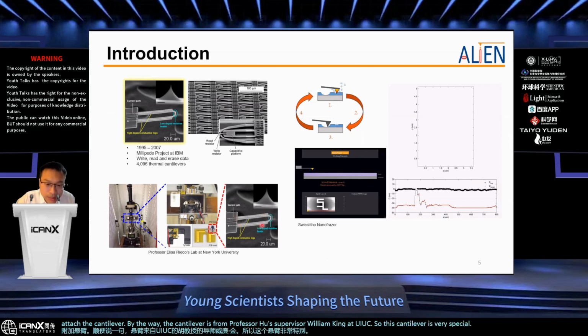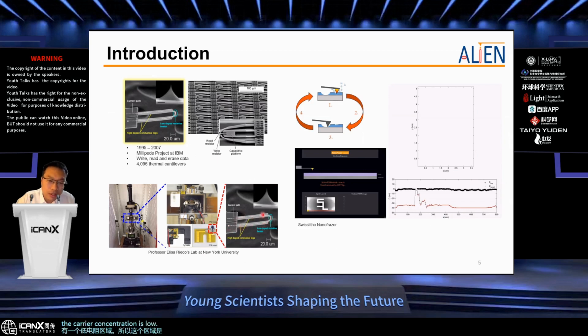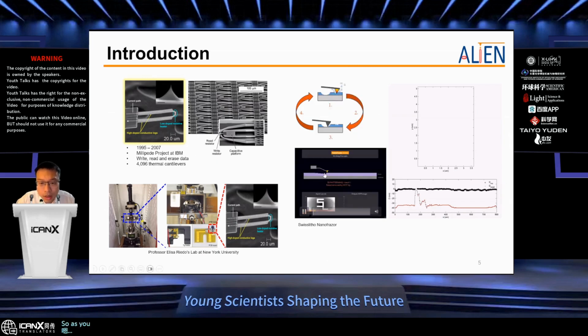As you can see here, it's made of silicon, but at the top of the cantilever, there's a low-doped resistive region. So in this region the carrier concentration is low, and in the bridging cantilever legs the carrier concentration is high. So if we flow a current or apply a voltage, we get Joule heating accumulated at the apex of the cantilever, and this heat can transmit into the tip apex, so that the tip can be heated and burn the polymers. I'll show you an animation here. As you can see, the tip is burning some polymers and creating structures, and during the retrace, the tip is measuring the contour, the topography, at the same time.